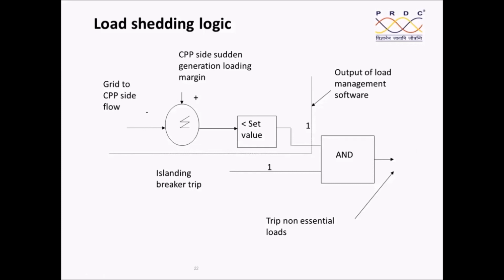Therefore, it is not just the islanding scheme logic. Over and above that, we also try to design our own control logic so that the islanding can happen, and post islanding, the load tripping can happen. Assume that the CPP side sudden generation loading margin is 3 megawatt. Grid to CPP side is minus 2 megawatt. Therefore, minus 2, 1 megawatt comes here. Assume that the set value is still 0. This is 1 megawatt, which implies there is no islanding load shedding.